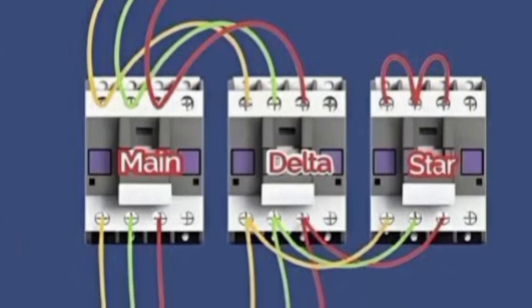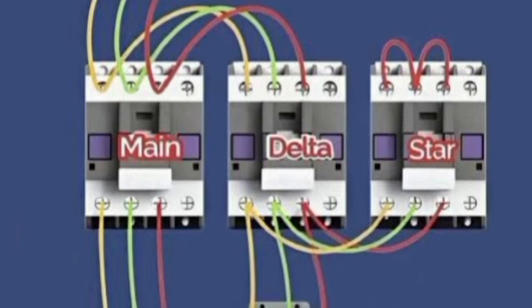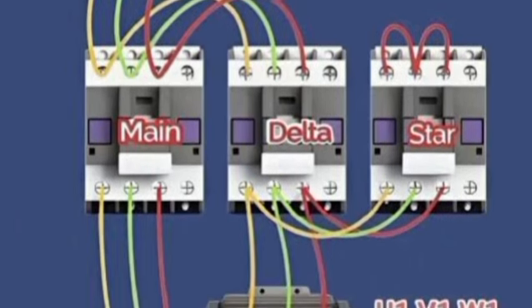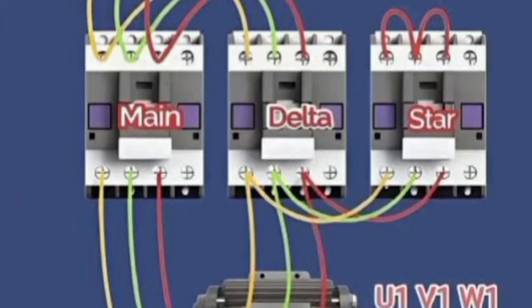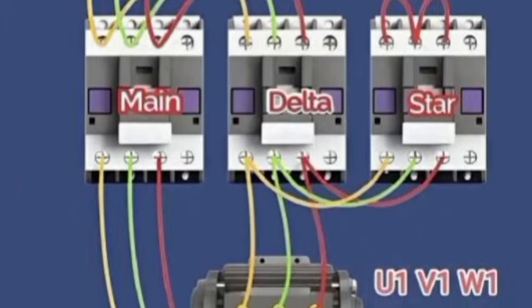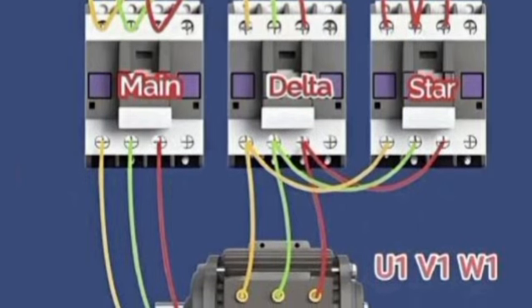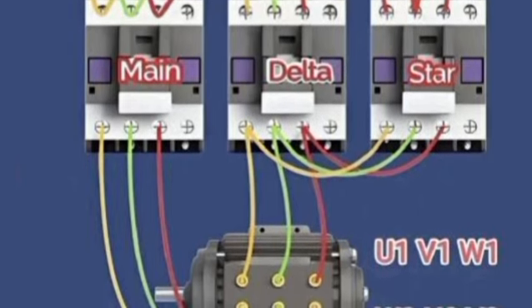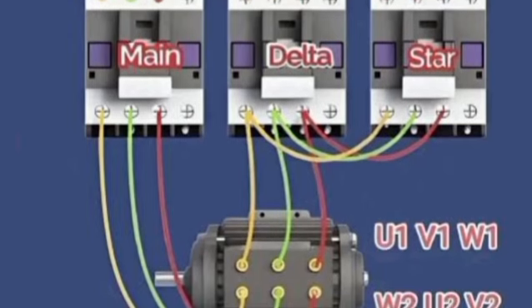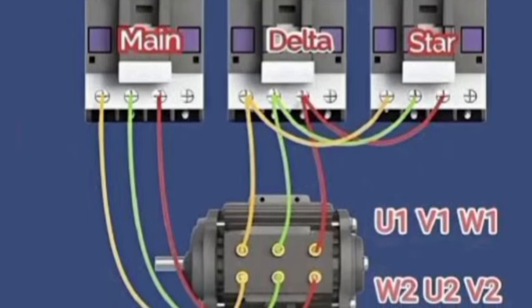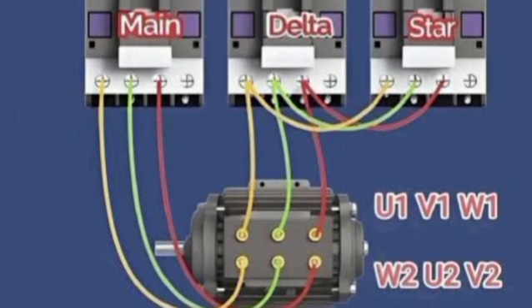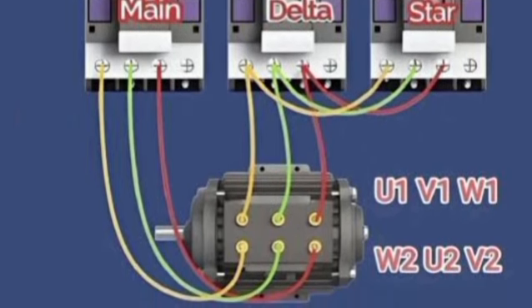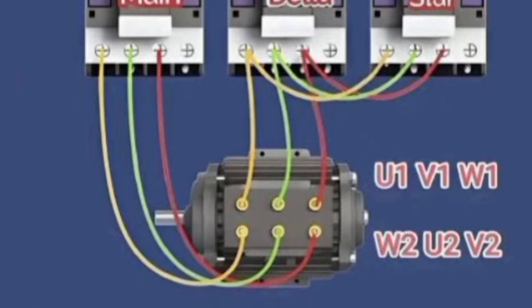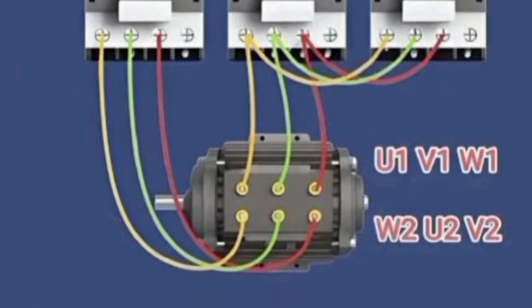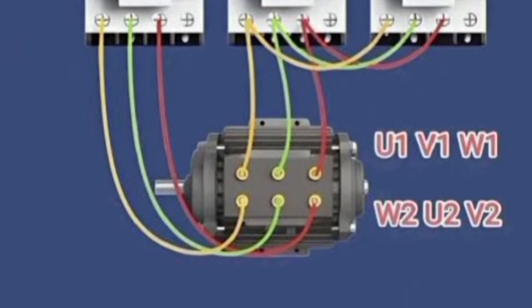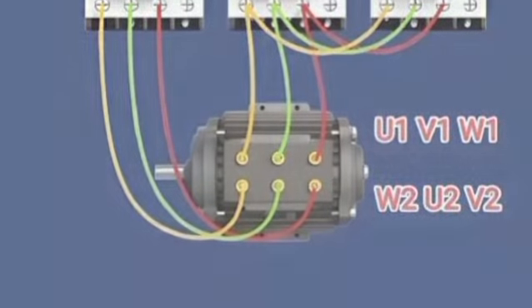in industrial setups. A star delta starter provides a controlled method of starting induction motors. Instead of applying full voltage instantly, it reduces stress during startup and then allows normal operation. Understanding why star delta starter is used helps explain its popularity in factories, pumping stations, and commercial facilities. Its balanced design makes it a reliable and practical solution for many motor-driven systems.